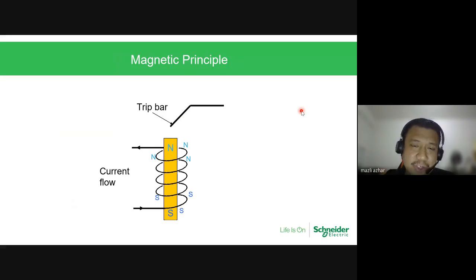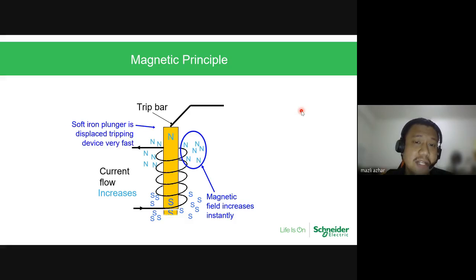Okay, so the magnetic principle. Inside the MCB we have a solenoid. If you see a magnet, it has a polarity, north and south. When the current flows at normal condition, nothing happens. But when the current flow increases, the magnetic field increases. So what happens when you take magnets with the same polarity? They will push each other, right? So this is where the principle comes in. With the same polarity, the solenoid here will be pushed and it will touch the trip bar to open the circuit. So this thing happens very fast, in a mere millisecond.